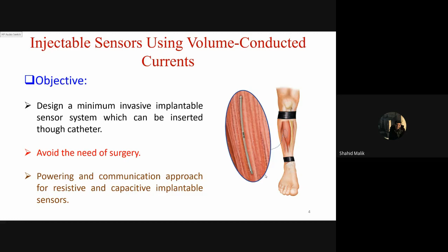So the basic principle of this approach is as shown in this diagram, where we have a burst generator, which is basically a sine wave generator or any external generator, which will directly supply the signal to the part of the body where we have placed our implant. And the only electronics we need inside the body for this approach is a rectifier and a capacitor. The rectifier will receive those high frequency signals from the electrodes placed on the body, rectify them, and slowly charge the capacitor, which is the implanted capacitor. So we are basically transferring power from an external generator through the body's conductive tissue to the implanted capacitor. But again, there are several issues which we need to take care of.